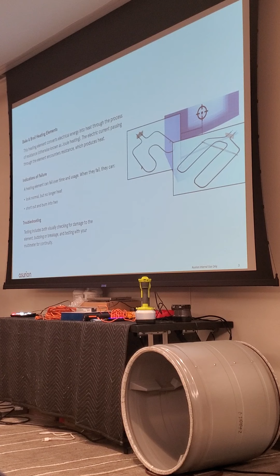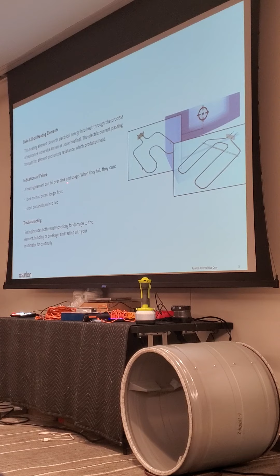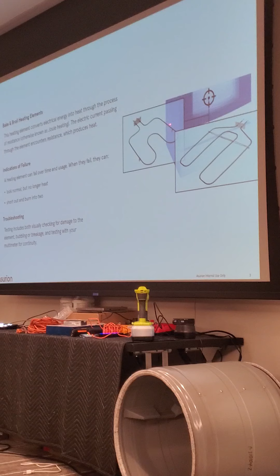Otherwise, they are a continuous filament heating element, so they'll continue to put out heat as it energizes and fires up and down as needed. A heating element can fail over time with usage. It can look normal but no longer heat, or it can short out and burn through. Sometimes they'll look fine on top and not work at all. You need to be aware of that.